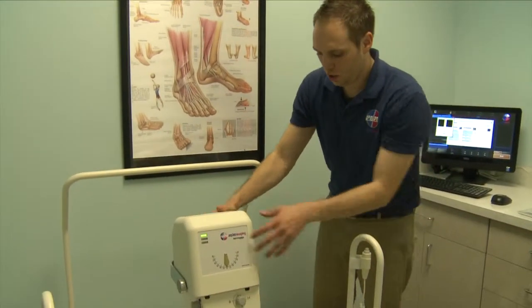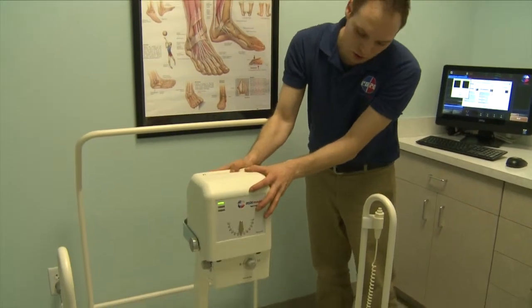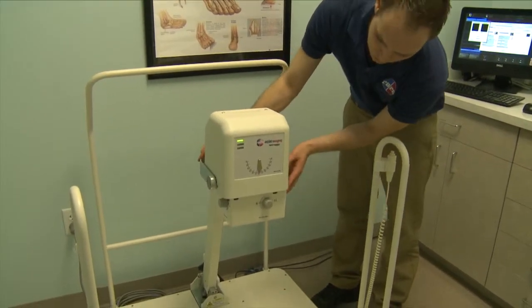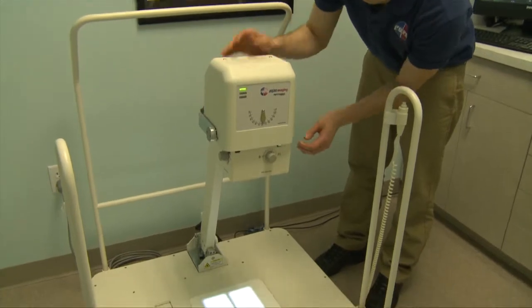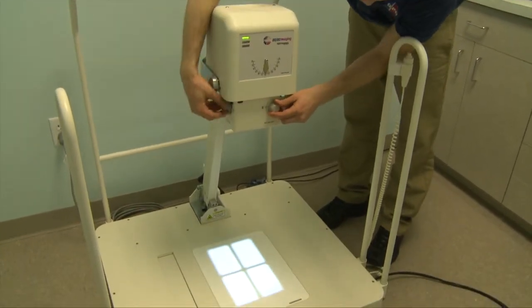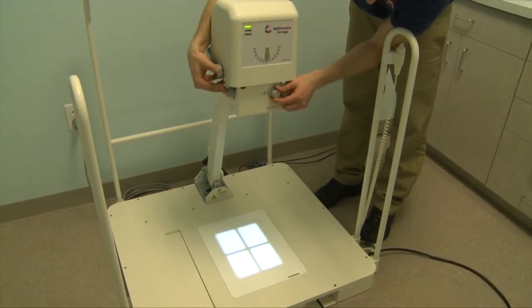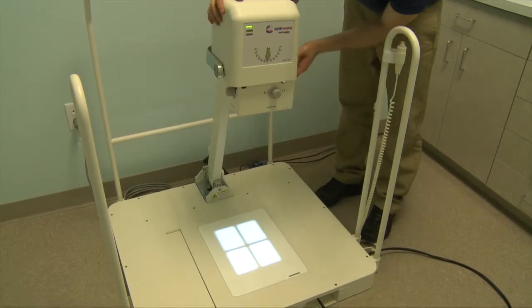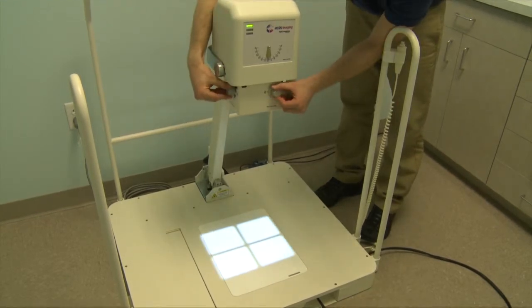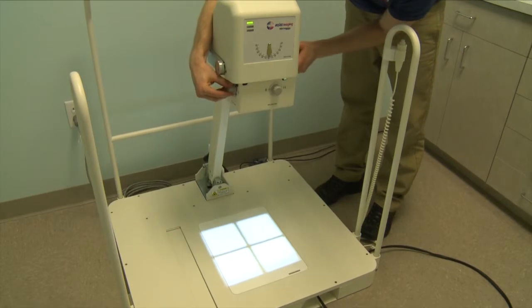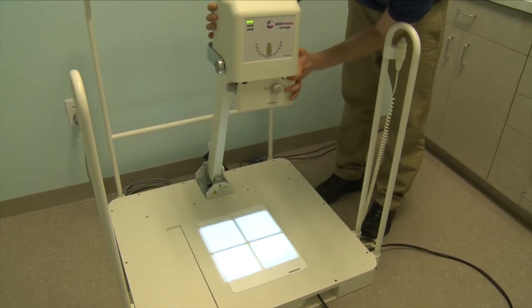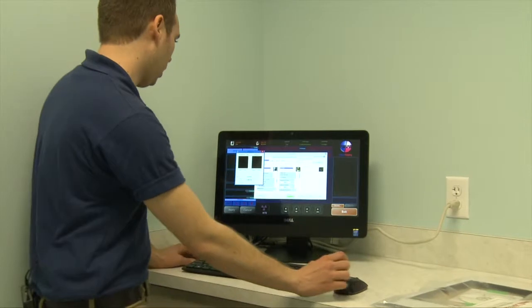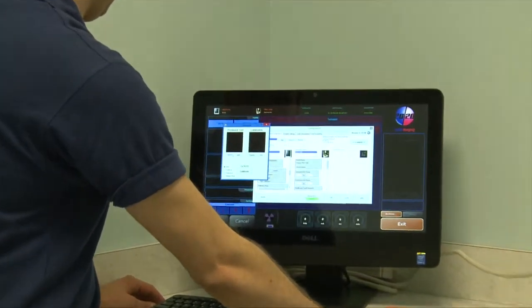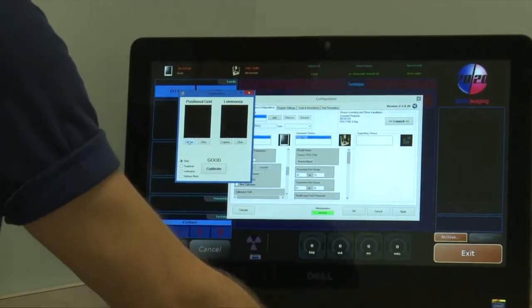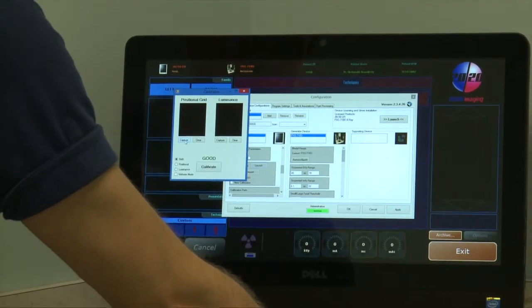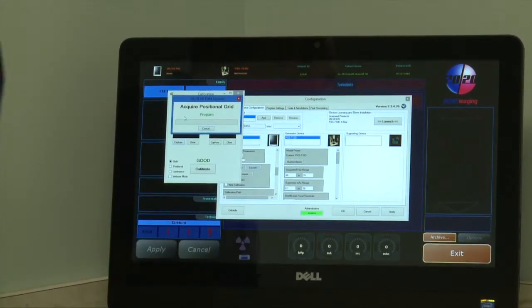Position the tube head straight above to be seated at 0 degrees. Line up the collimators so it is centered directly above the panel. Once you have it centered, simply open the collimator light up as far as it goes. Back at the computer, we're going to prepare the shot by clicking the capture button for positional grid. And we're now ready to take our exposure.